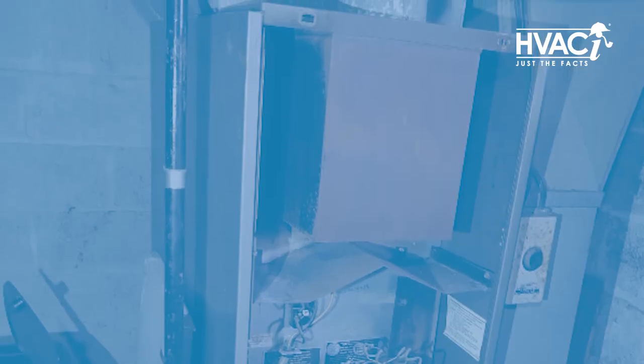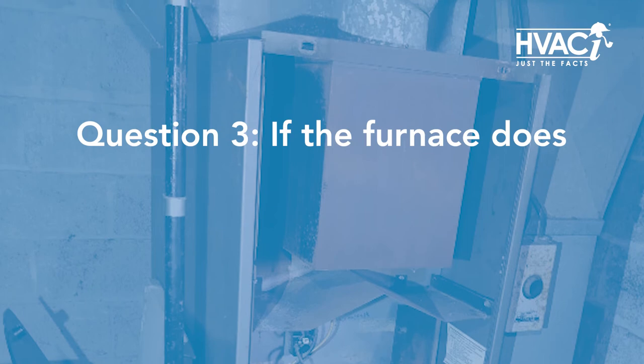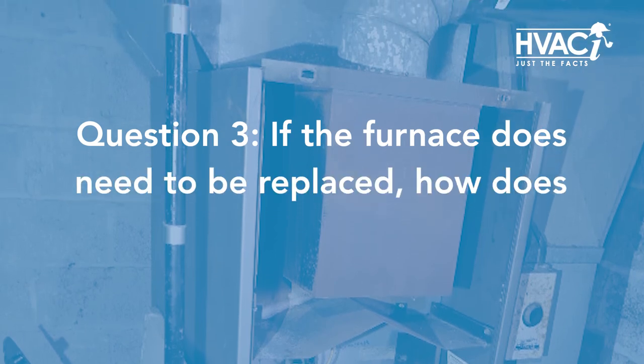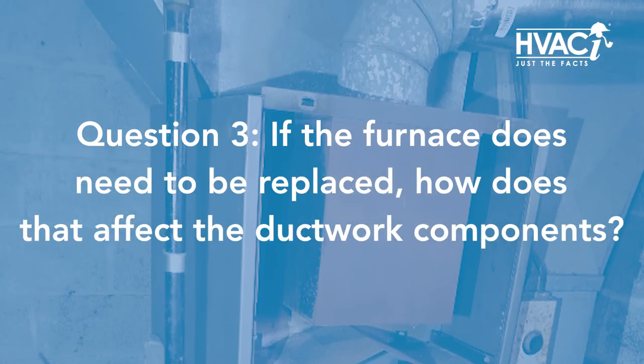Our next question has to deal with furnaces: if the furnace does need to be replaced, how does that affect the ductwork components? That depends on how compatible the new unit is with the unit being replaced. If it's the same make and model, there's a good chance it will fit right in, and we can use the same ductwork and connections. But if it's a newer unit, maybe a different size, or we've had to change brands, then we're probably going to have to fabricate some ductwork connections on site to make that work.